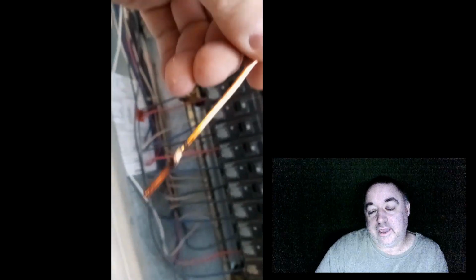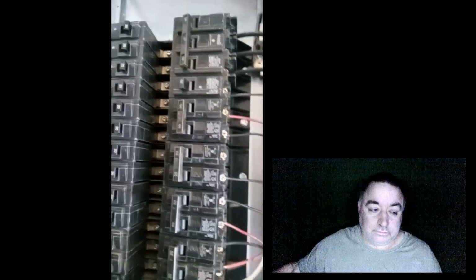Now the machine does not call for a neutral. I looked at the paperwork. I talked to the guy on the phone. He said hot ground. So, if that machine is pulling that kind of power on a neutral side, it should be an insulated wire. Check the manufacturer specs. It's got the right outlet that it calls for that machine. It does. So I cut our burnt piece out right here somewhere. And I reattached that, nice and strong. It was loose, and you can definitely tell it was arcing. See that darkness? That's right where it is. I moved it up. And that neutral wire is okay.